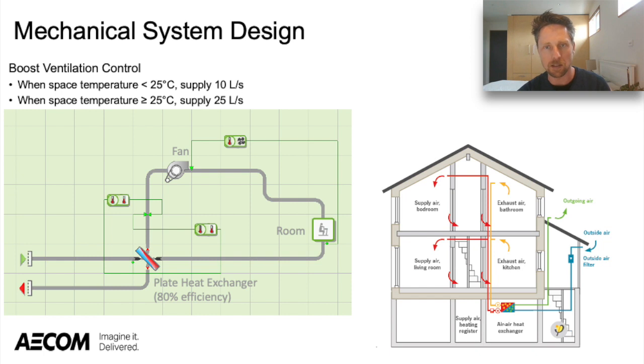For mechanical system design, we went for a relatively conventional passive house design with heat recovery systems operating at 80% efficiency and no active heating and cooling. We did consider having these heat recovery systems located in each individual space. However, given the impact on occupants if units broke down and needed access into their spaces for maintenance, as well as additional facade penetrations - with 150 beds, that's quite a number of facade penetrations - we then pushed for large central heat recovery systems instead.